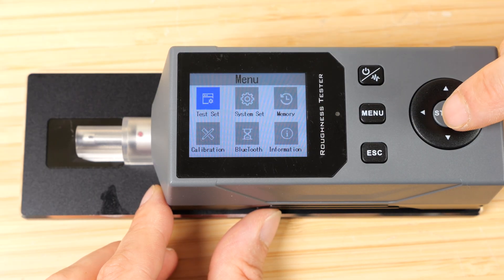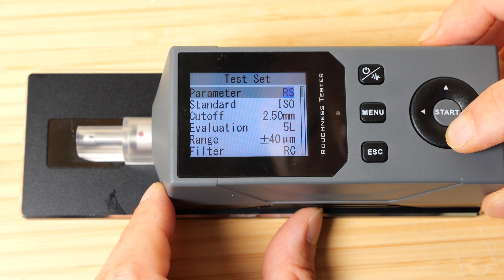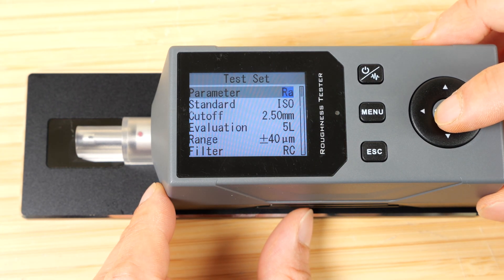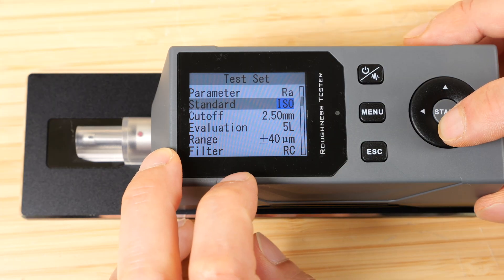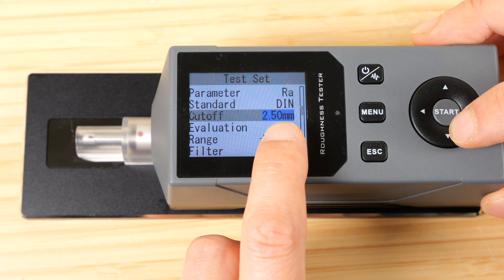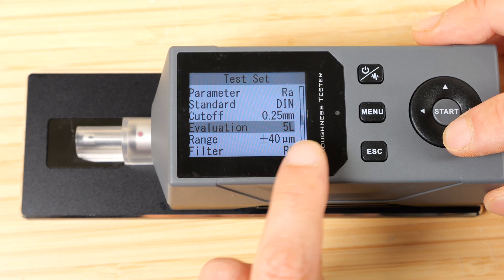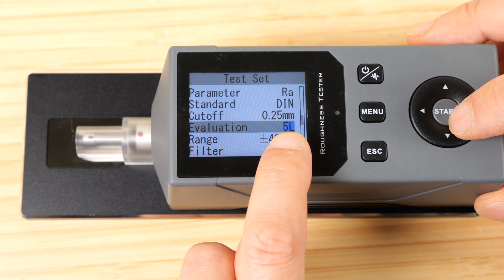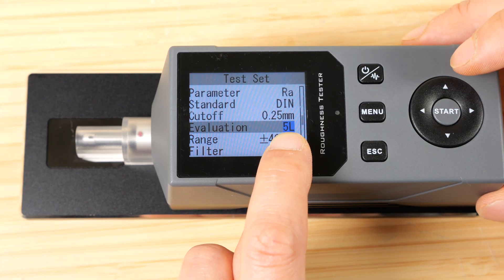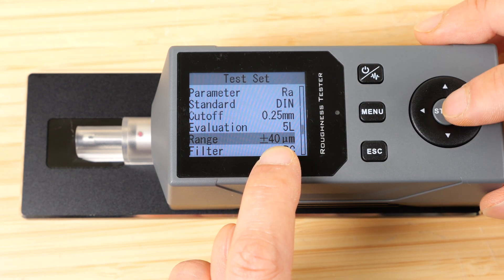You can change any of these parameters. Just press menu, test set, press start. The parameter options are RPC, RKU, RSK, RSM, RS, RV, RP, RT, RZ, RQ, RA — I'll leave it at RA and press start. You can change the standard from ISO, ANSI, JIS, or DIN. The cutoff is the duration for each measurement: 2.5 mm, 0.8 mm, or 0.25 mm. You can do one to five evaluations. The range is the expected height variation — plus or minus 40 microns.